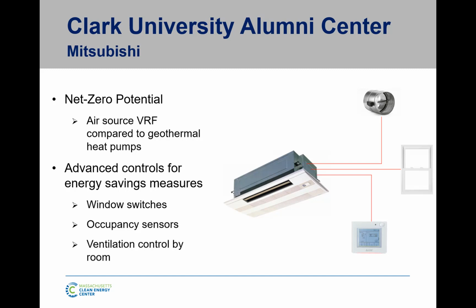Then on top of that were window switches, and these all tie directly into the fan coil. So you open the window, the ventilation damper closes, and the unit shuts off. And there were alarms and safeties built in, so if it got below 50 degrees, it would alert the facility manager that a window's open so they could handle it.